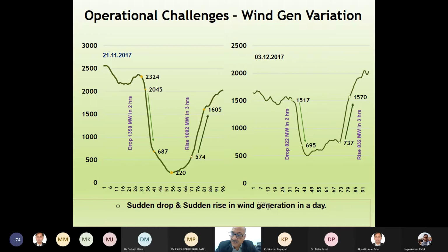Now we are going for flexibility issues, and with flexibility we need certain modifications and renovation in the machine so it can run down to 35% of load. If we make our machines able to run at 35% capacity of the total installed capacity, then naturally we have cushion.